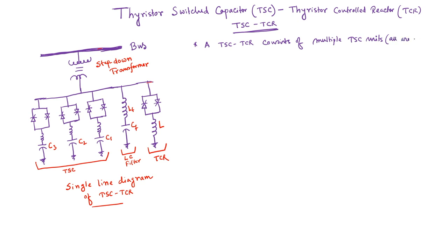All are identical, single or multiple TCR unit. Usually this number of TCR unit is kept less, so that the total harmonic generation by this TCR operation is also less. In fact, normally the common practice is that even in this case of TCR, we keep some thyristor switched reactor, that is TSR, and some TCR, only one or two as TCR, so that the total harmonic generation by the TCR would be less.